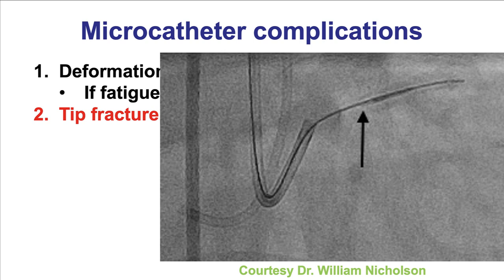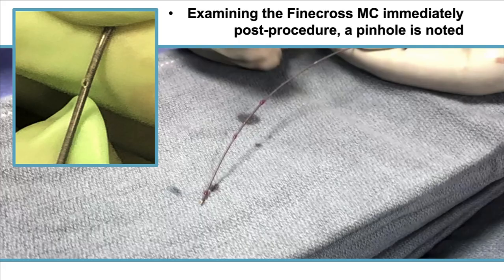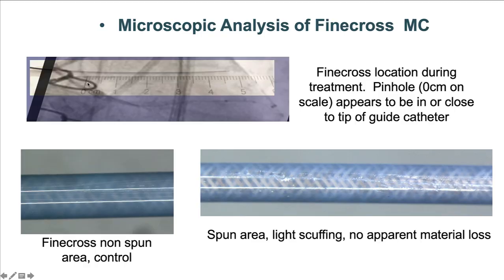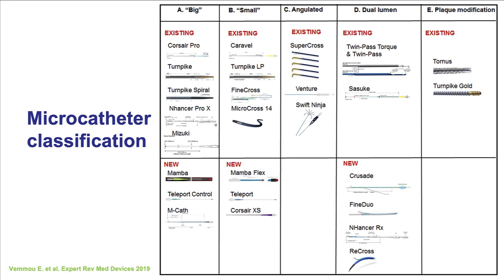Also very important: every time there is manipulation of the microcatheter, a guide wire should be inside the microcatheter lumen. Another complication is fracturing of the tip — this is more common for microcatheters that have a softer tip, and those should probably be avoided in heavily calcified and resistant lesions. A microcatheter should not come in contact with another piece of equipment, microcatheter, or balloon over the same guide wire, as interlocking can occur. Additionally, microcatheters have been used to protect side branches during atherectomy, but this is not foolproof — in one example, a Finecross used to protect a side branch was actually perforated at the site of contact with the atherectomy device.